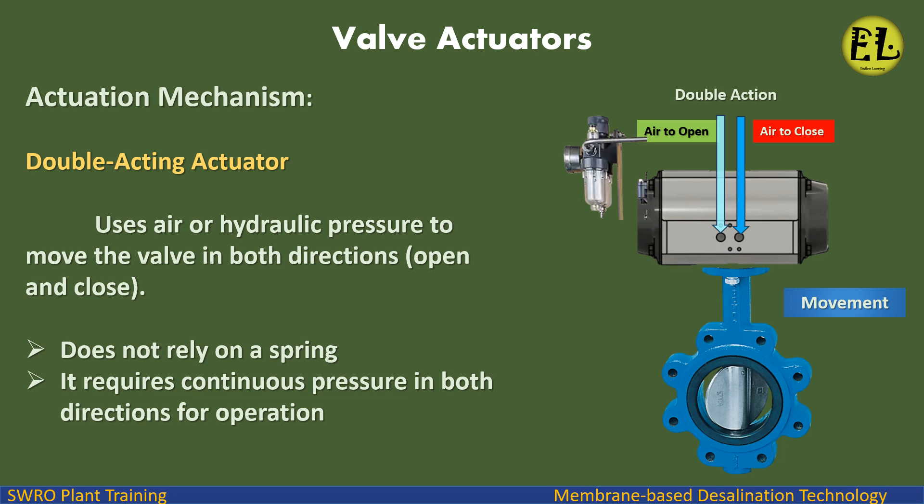Actuation mechanism — double acting actuator: uses air or hydraulic pressure to move the valve in both directions, open and close. Does not rely on a spring; it requires continuous pressure in both directions for operation.